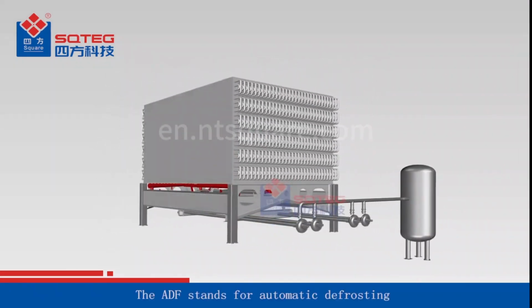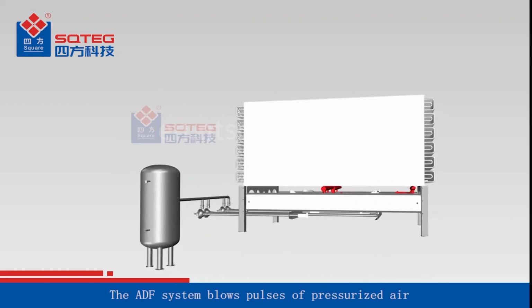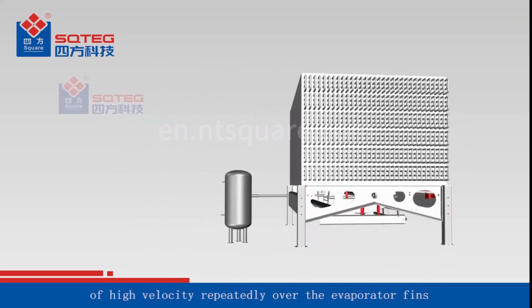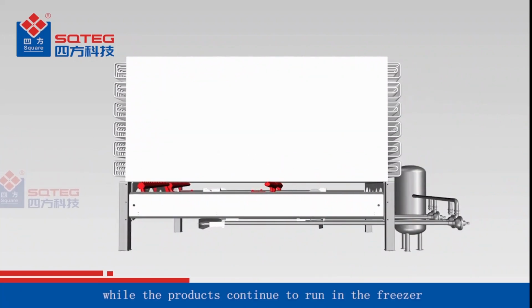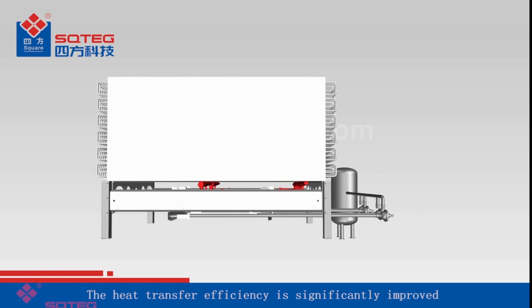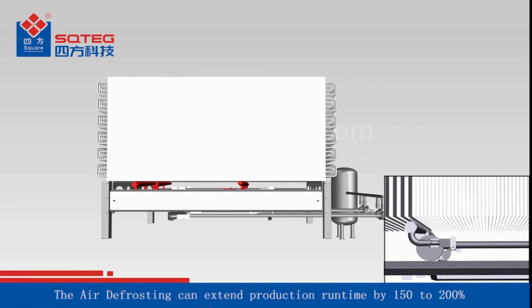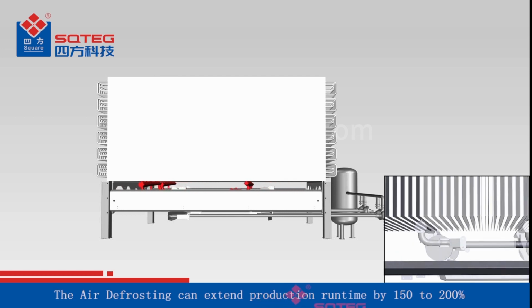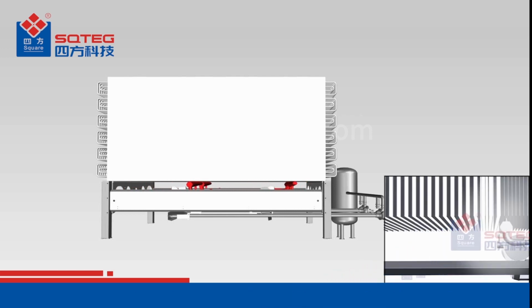The ADF stands for automatic defrosting. The ADF system blows pulses of pressurized air of high velocity repeatedly over the evaporator fins, to remove the frost, while the products continue to run in the freezer. The heat transfer efficiency is significantly improved. The air defrosting can extend production runtime by 150 to 200% by eliminating frost buildup on the evaporator.